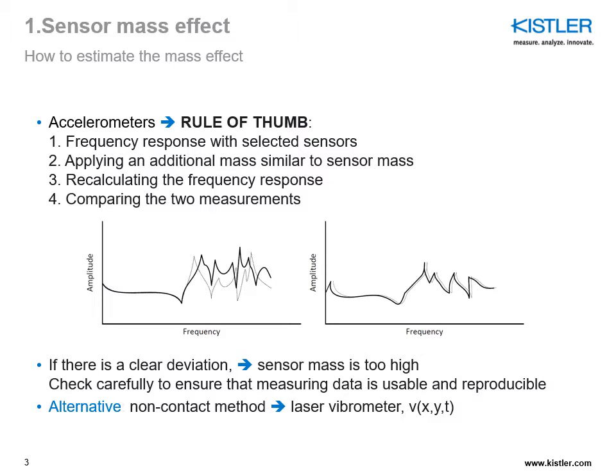Another alternative, if the sensor mass is too big and cannot be reduced, is to go for a non-contact method, such as a laser vibrometer as discussed in the first part. In the next slide, there is a small movie showing a very simple basic demo to show how this resonance frequency can change due to the mass of the sensor.